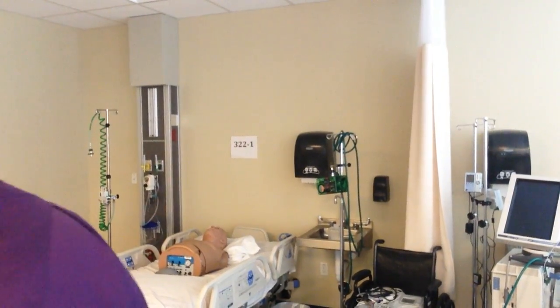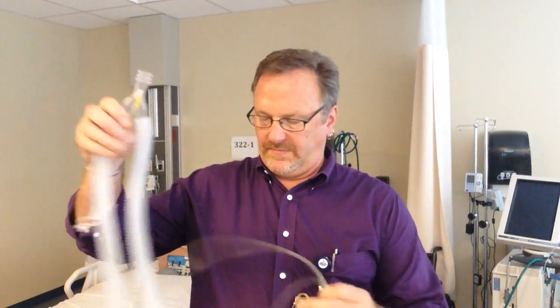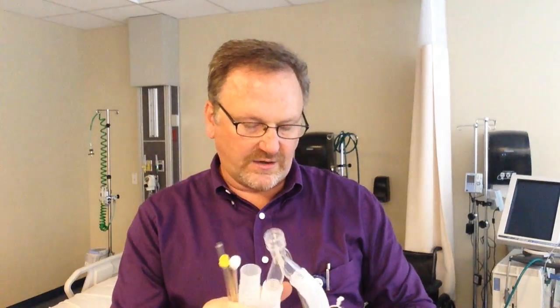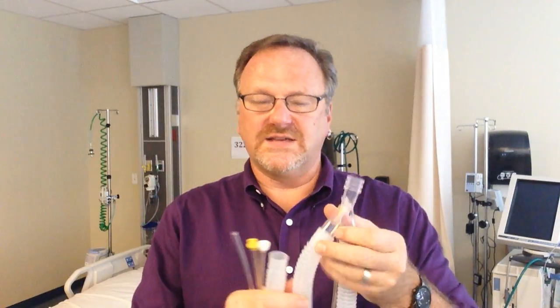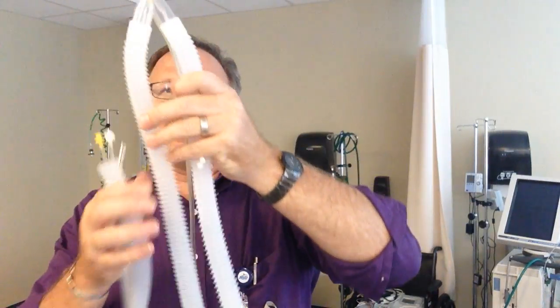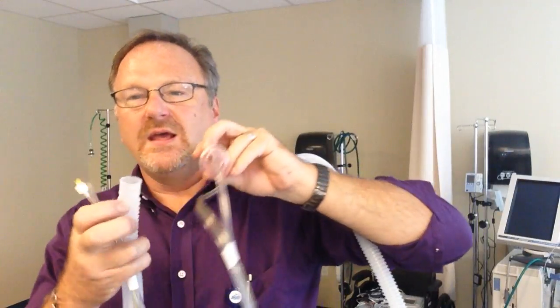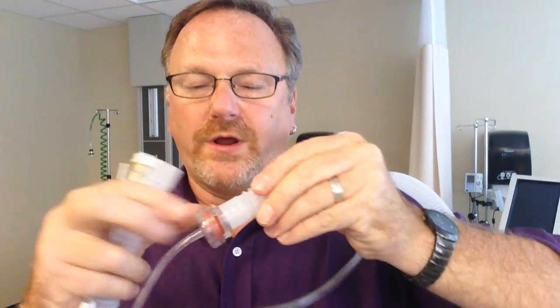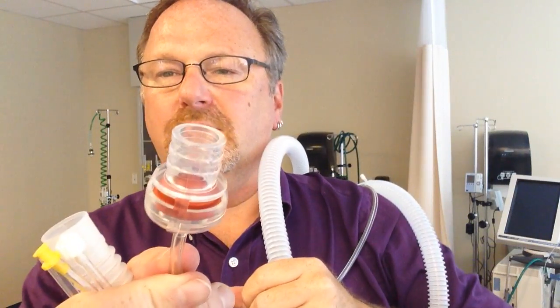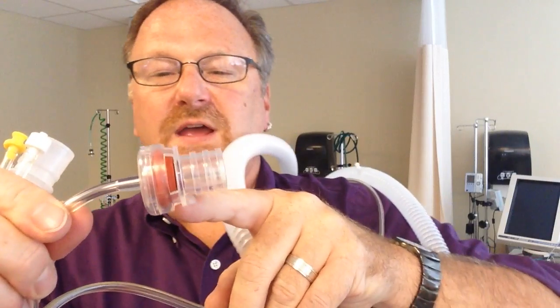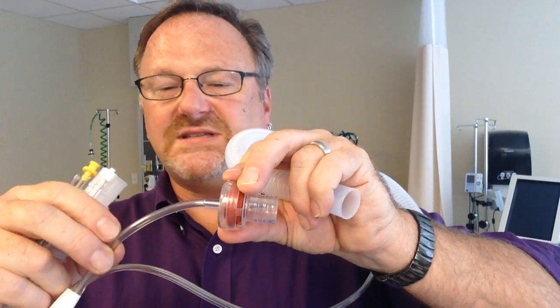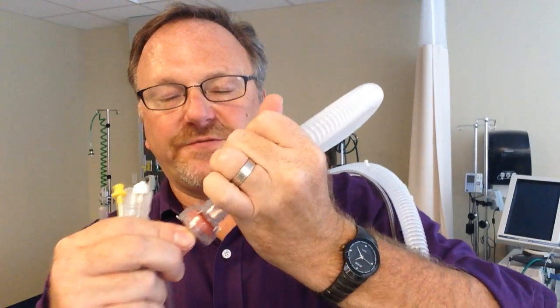The last circuit that we're going over is an LTV circuit. These are a little different. They do come in a heated wire and non-heated wire. There is an LTV setup video that is on our channel, so watch that on how to set this up exactly. Now this one does not have heated wires, but there is an inspiratory limb and expiratory limb. The LTV has what we call an external expiratory valve. It is a little mushroom valve that when the patient needs to inhale, pressure comes in here, inflates this little mushroom valve, and prevents the patient from exhaling, such as the other ventilators all have it internally.